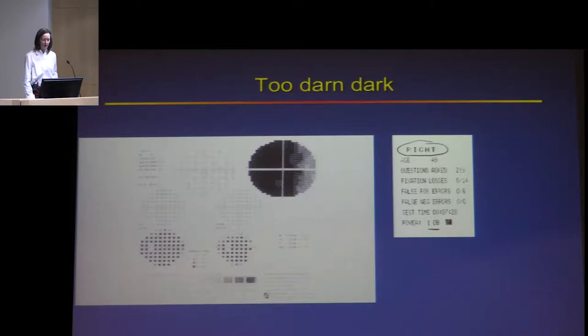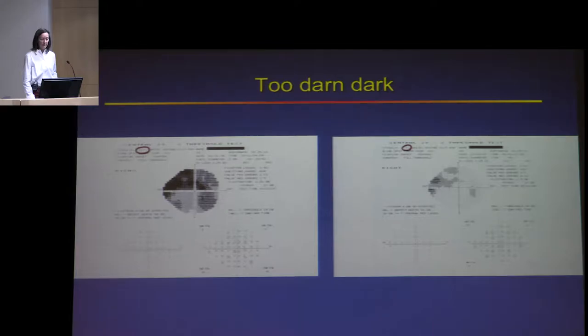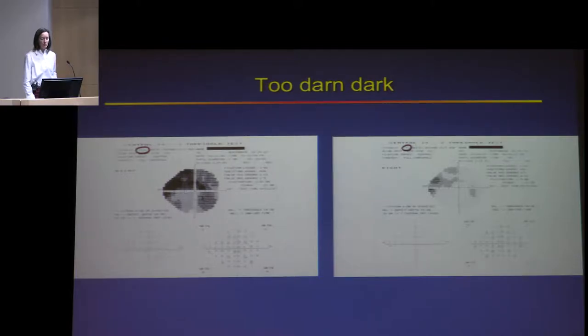What about that one? The foveal threshold there is one decibel — that can't be good. It's just too dark; you can't do that test. This is not a problem with the machine, it's a problem with the choice of test. With the size-3 stimulus they can't do much, but with the size-5 stimulus you can actually follow the patient. The one on the left is a size-3 stimulus; the one on the right is a size-5 stimulus.